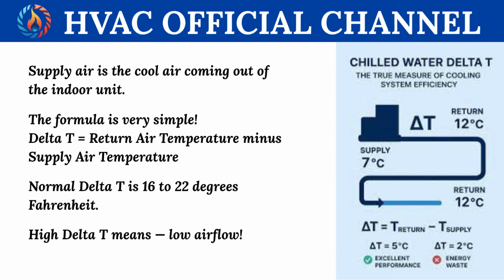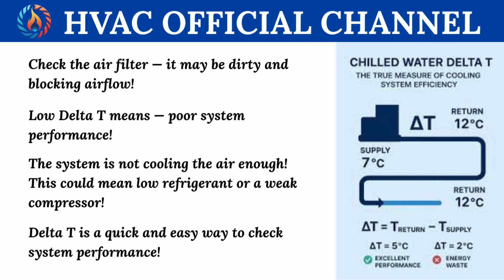Normal delta T is 16 to 22 degrees Fahrenheit. High delta T means low airflow. Check the air filter. It may be dirty and blocking airflow. Low delta T means poor system performance. The system is not cooling the air enough. This could mean low refrigerant or a weak compressor. Delta T is a quick and easy way to check system performance.